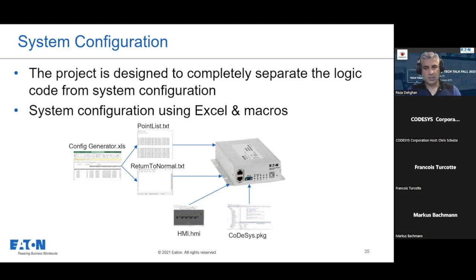And to feed the code to SMP Gateway, one way would be always to use the CODESYS workbench, but because this one is a final product, you don't really need to change the code. What we do is we just create a package file, and once we push this package file to SMP Gateway, it will extract the package file, which is a kind of zip file, and put the elements of a soft PLC at the right place so the code can be executed. And then at the end, there is another file too, which is our file for the HMI.